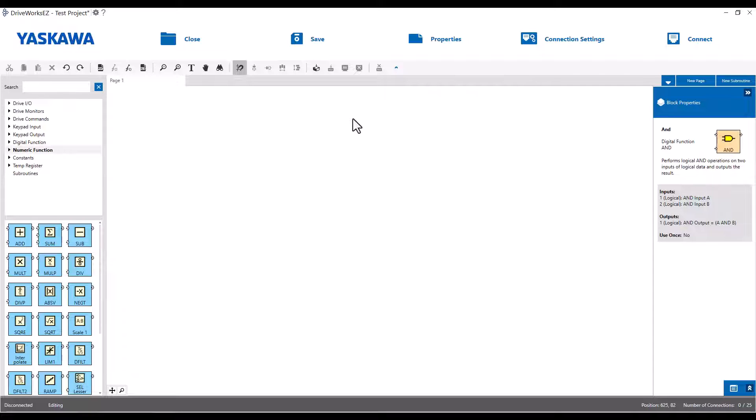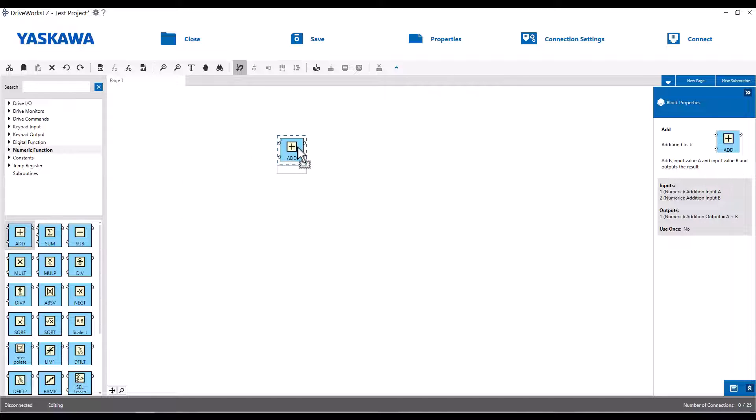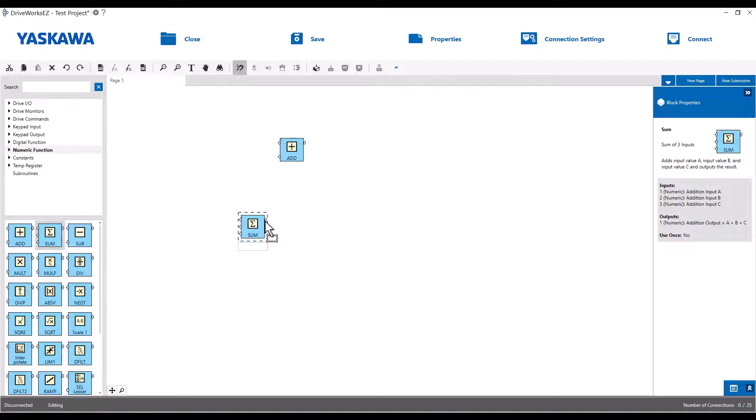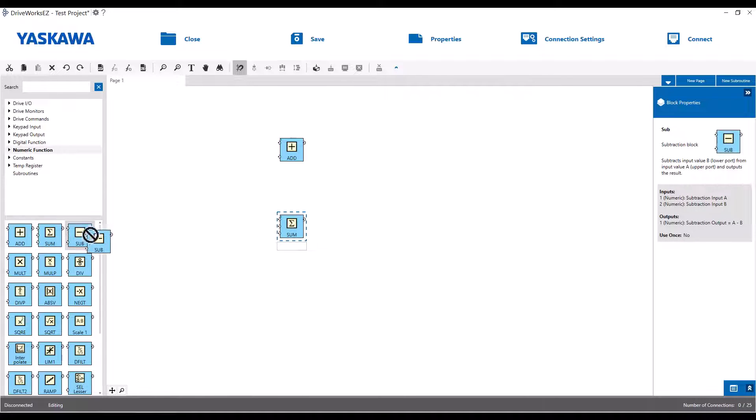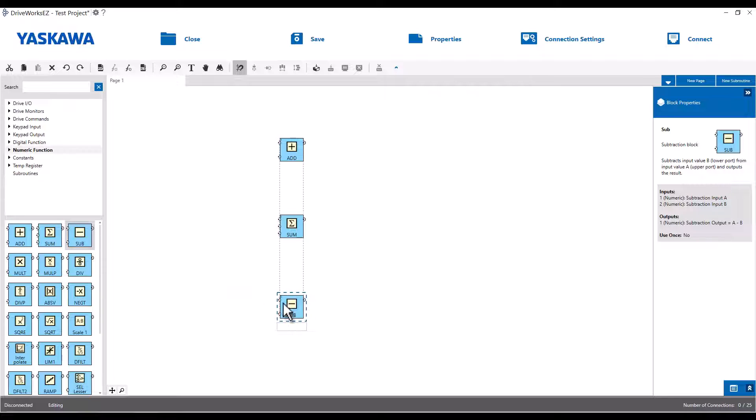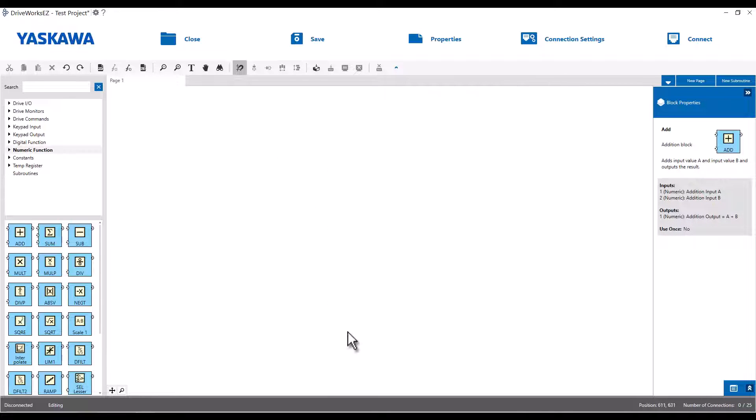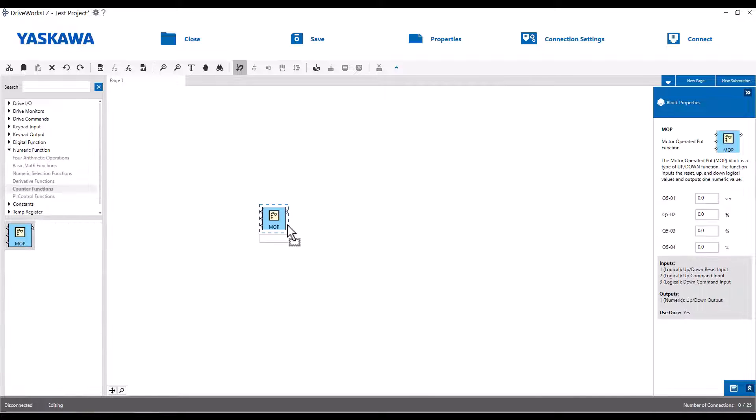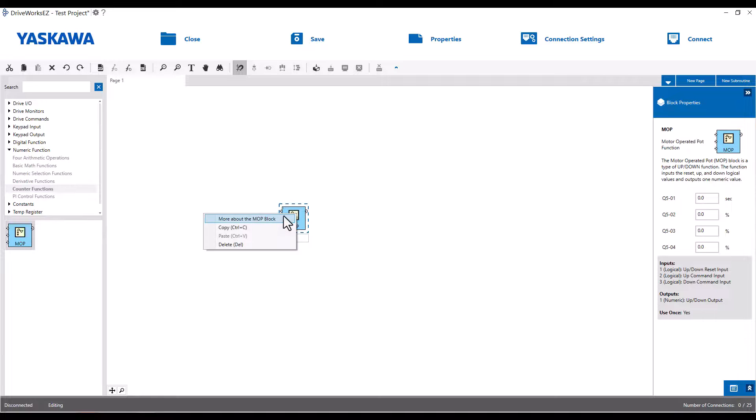Numeric functions will take numerical inputs and produce a numerical output. For example, I can use the ADD block to add two analog inputs together. A SUM block will output the sum of the three numerical inputs. The SUB block will output the difference of the top input minus the lower. There are a couple of ways to multiply and divide inputs. Make a value an absolute value, scale a value, filter it, ramp it, limit it. These are all at your disposal in the Numeric Function tab. Some of the function blocks listed under the Numeric Function heading will actually include logic inputs to the blocks as well.